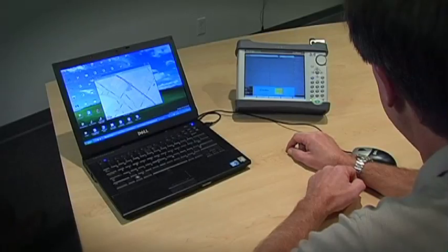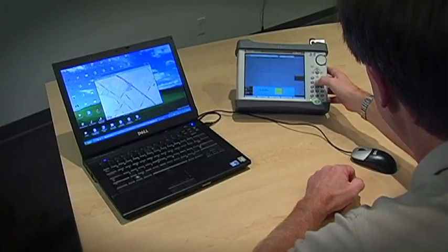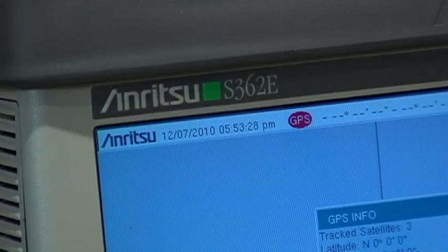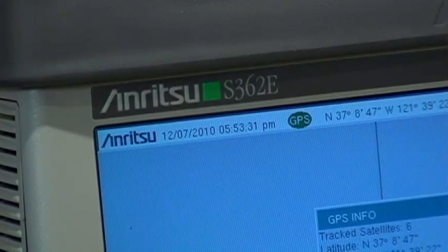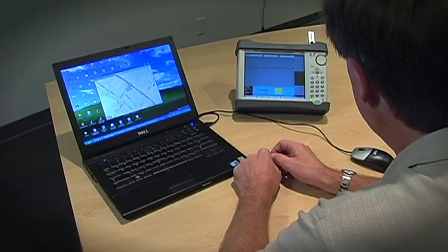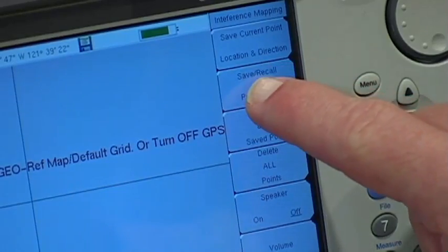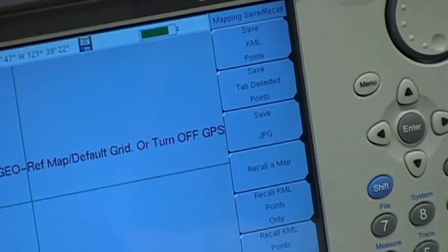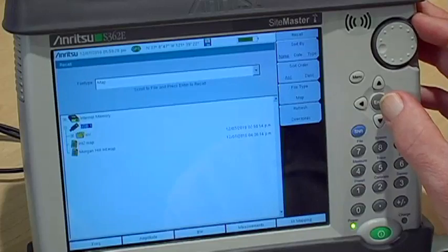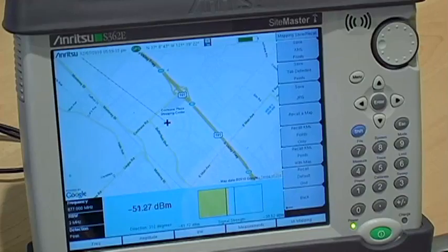Interference mapping also requires the use of the GPS function. You can turn the GPS on or off and change other settings through the GPS submenu. Once GPS is on, the instrument locks on to at least three satellites and you can now interference map. GPS is now on, so you can open the map file just created. From the interference mapping menu, go to Save Recall Points Map and press Recall a Map. Find the map on the USB and press Enter to open it. The image from the converted map then appears on the instrument's screen.